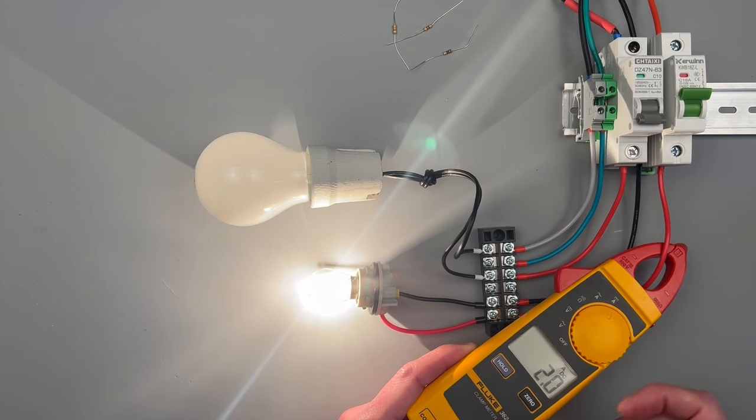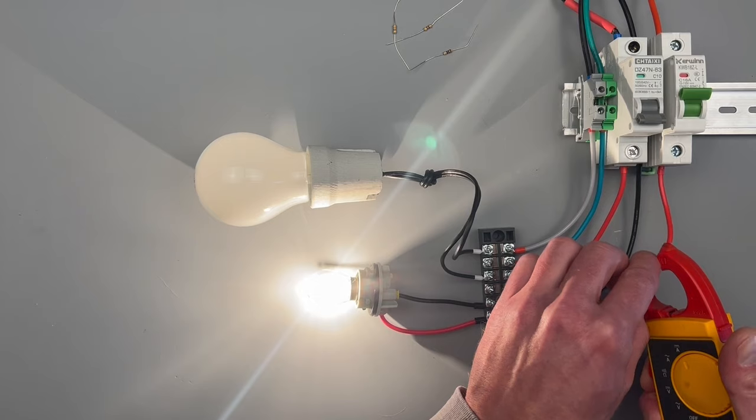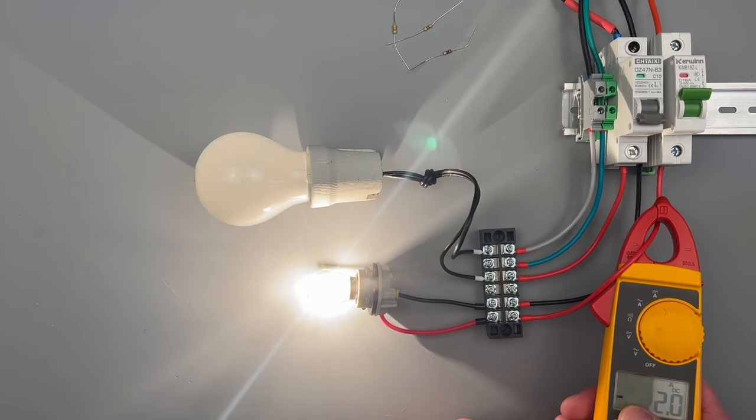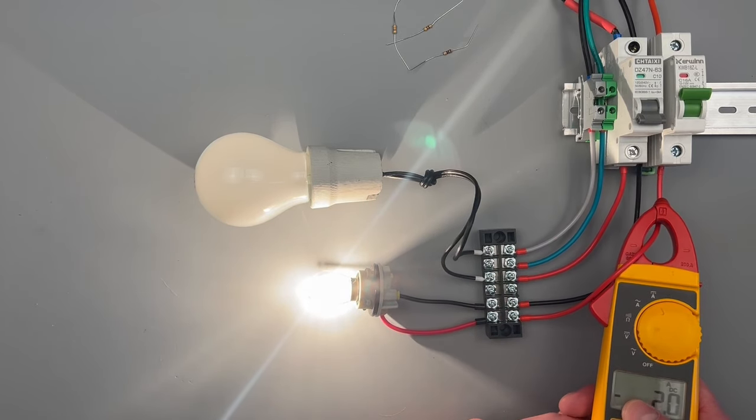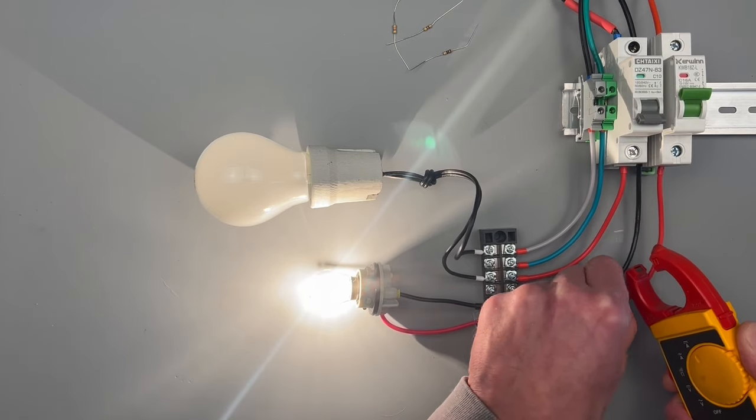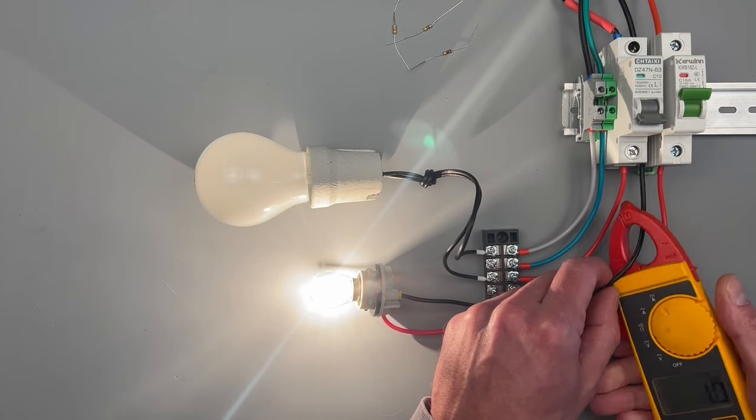Something with the DC amp clamp, you're going to notice it will have polarity annotated on there for you. So it'll have that negative sign. If I did the common side of my DC circuit depending on the way that I've fed my conductor through the amp clamp, it'll have a polarity indication.